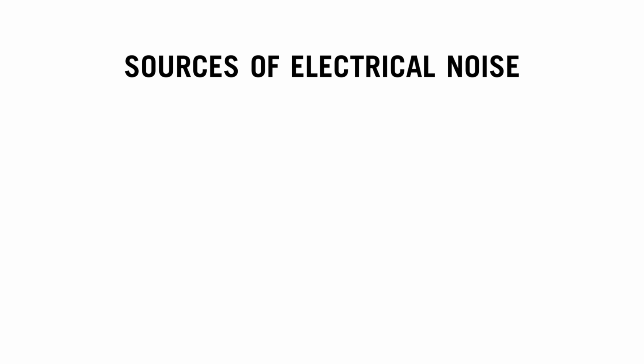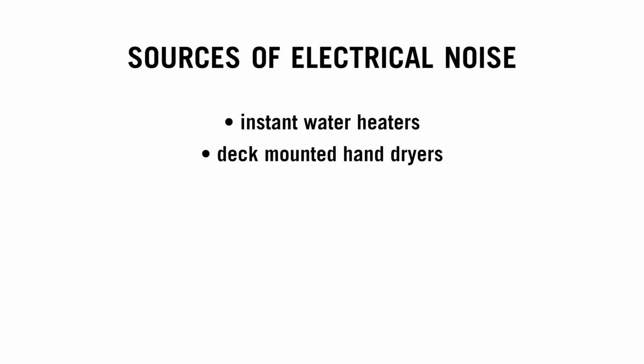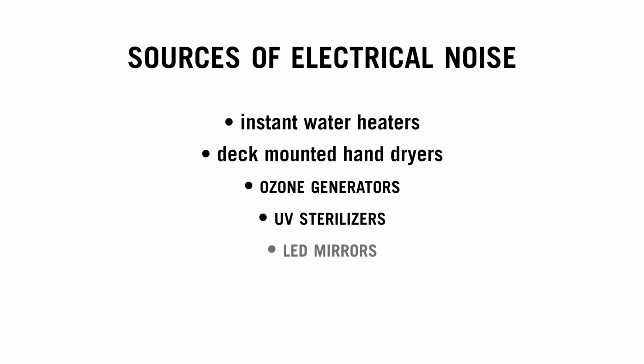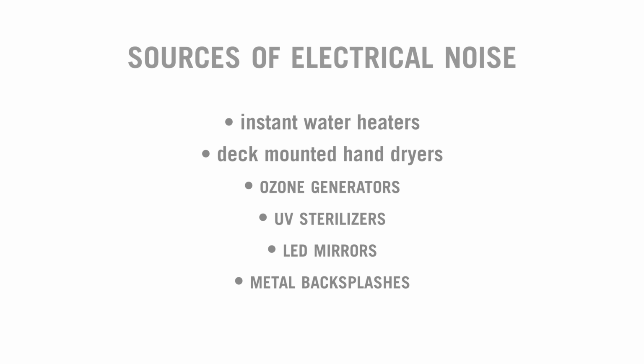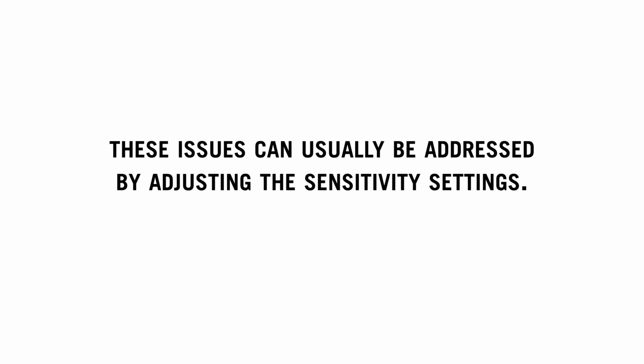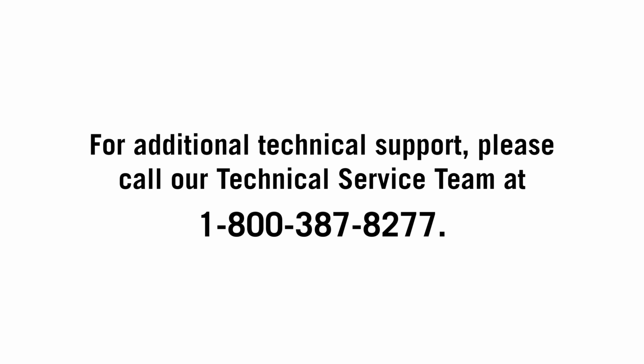Sources of electrical noise could cause interference with the capacitance field. This includes items such as instant water heaters, deck-mounted hand dryers, ozone generators, UV sterilizers, LED mirrors, or a metal backsplash. These issues can usually be addressed by adjusting the sensitivity settings. If none of this helps, please watch our troubleshooting video called Faucet and Soap is Not Working, or call our Delta Commercial technical support team.